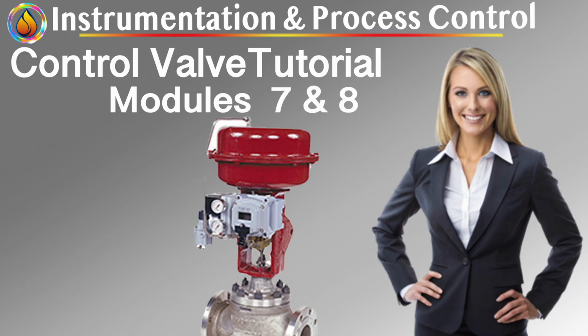Why stroking time is misleading. Full stroke time is often specified and often meaningless. Problems with using stroking time: it ignores friction thresholds, ignores mid-stroke dynamics, does not represent normal operating range, and overemphasizes actuator speed. A valve that strokes fully in 2 seconds may still take several seconds to respond to a 1% change, which is what control actually needs.